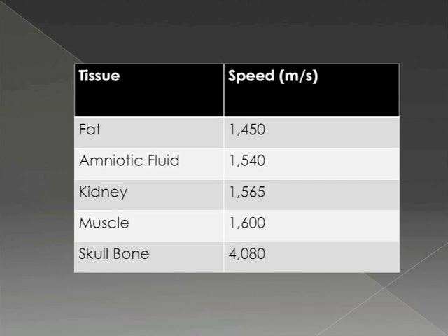Starting off, sound isn't like light — it doesn't have a constant speed. As it is a longitudinal wave, the medium that it travels through is what impacts the speed — the physical properties of that medium. These are just a couple of speeds for common tissues that we look at with ultrasound, and you can see that most of them are right around the 1500 range. Most ultrasound machines actually use an average speed of about 1500 to calculate depth when they're forming an image.